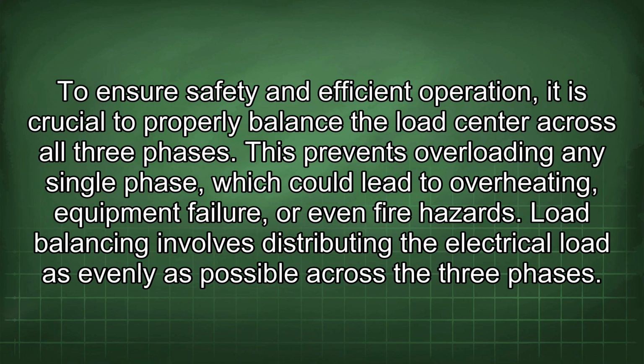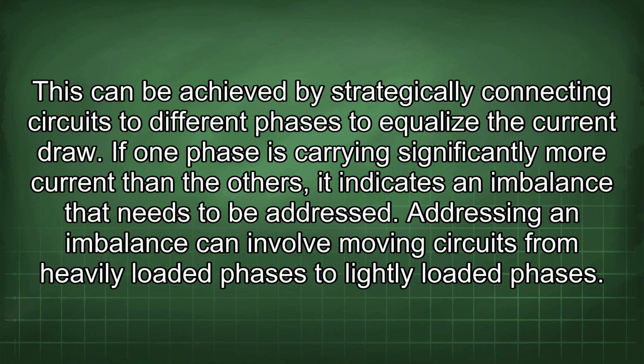To ensure safety and efficient operation, it is crucial to properly balance the load center across all three phases. This prevents overloading any single phase, which could lead to overheating, equipment failure, or even fire hazards. Load balancing involves distributing the electrical load as evenly as possible across the three phases. This can be achieved by strategically connecting circuits to different phases to equalize the current draw. If one phase is carrying significantly more current than the others, it indicates an imbalance that needs to be addressed.